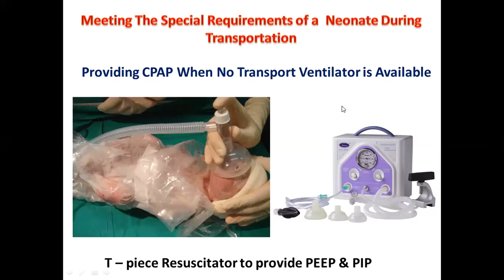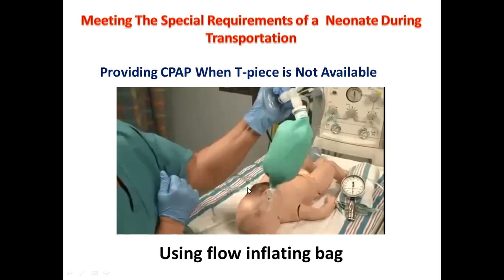So when we cannot afford to buy T-pieces, we can go for a flow inflating bag. See, the trouble is the same. We can't use blended oxygen, but there is a small hole over here. I'm not able to show you, maybe next time I will show. There's a small valve there, so that by Venturi effect, if the oxygen saturation is going good, we can just unscrew it, and air will go inside. To some extent, a little bit of blending can be done. So this can be used in this manner to provide CPAP when a T-piece resuscitator is not available.